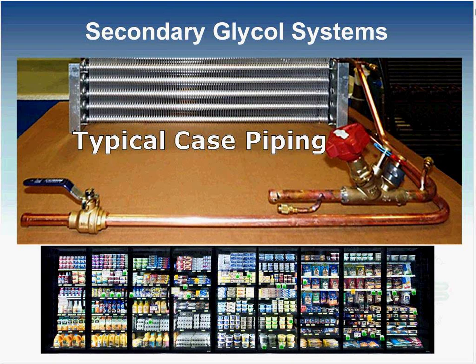If you went into your grocery store and watched the technician take apart the case, you're going to have a little bit larger copper lines inside the cases, because you are pumping it out to the case and getting the same liquid coming back. You'll have a little bit different valving inside the case to control the flow, because a lot of times some equipment needs more flow to be cold, other equipment needs less flow, so valves will be set in there to adjust it. From a floor perspective, customers will just see product in the cases. They won't see any of this. It'll be beneath the floor case or in the back wall.